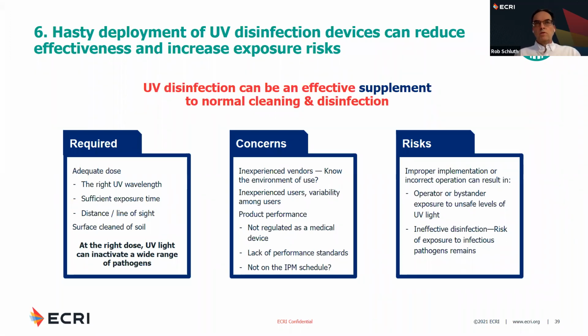Now, ECRI has tested UV disinfection devices in the past and found that they can be an effective supplement to normal cleaning and disinfection. So at the correct dose, the right wavelength of light, UV light can inactivate a wide range of pathogens. It does that by damaging the DNA and the RNA structures to prohibit replication. But that requires that you have an adequate dose. Like I mentioned, the correct wavelength of UV light, not all wavelengths will be appropriate. Sufficient exposure time: the surface has to get enough of that light for it to take effect.